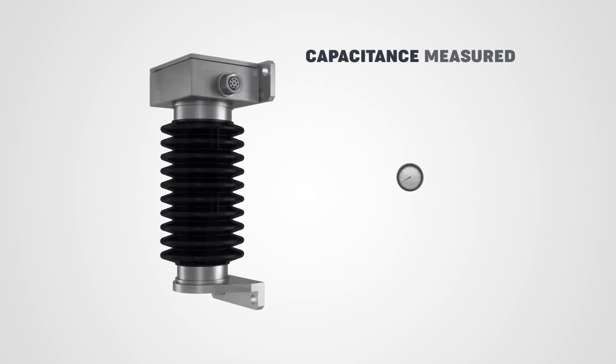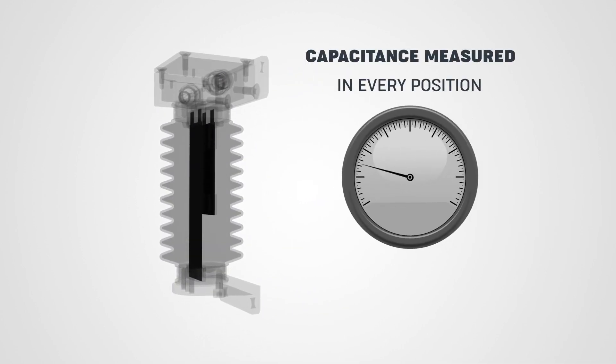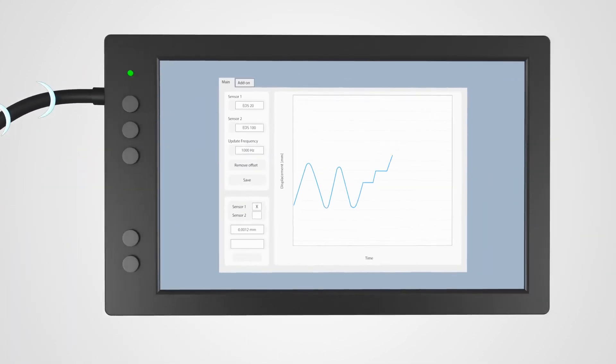This enables measurement of both linear and off-axis displacements. When installed and stretched by a machine or structure, it causes a change in the elastomer's capacitance, which is measured by the integrated data acquisition electronics. This information is then transmitted for monitoring and control of a system or process.